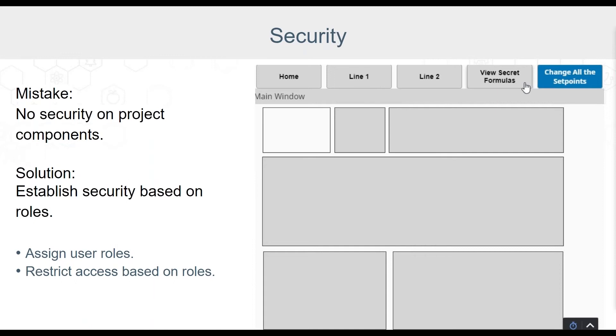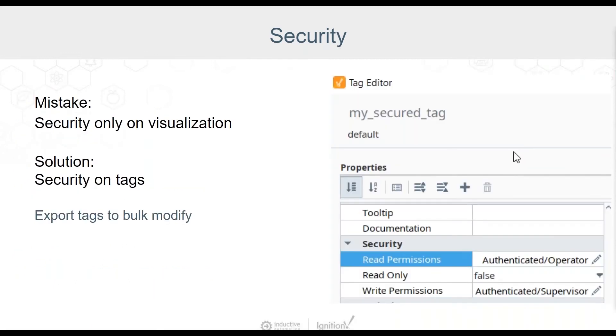Vision windows and components can be protected by right-clicking on any object and choosing Security. Perspective resources can be set to disabled or invisible by binding to expressions for role memberships. Once we have roles on our visualization components, we should also think about tag security. This will ensure that even if a component somewhere in a project allows access to a tag, the user still must meet security requirements to view or write to that tag. You'll first want to set up security levels, then assign those levels to the read and write permissions on your tags.